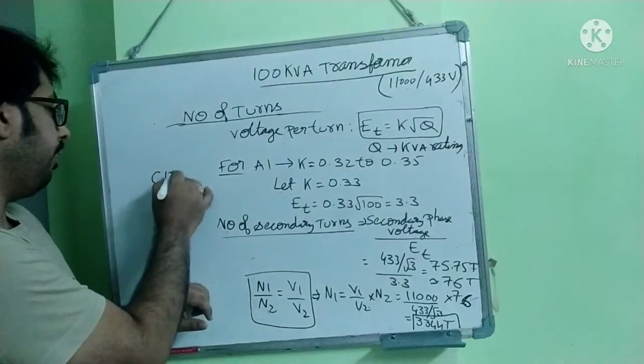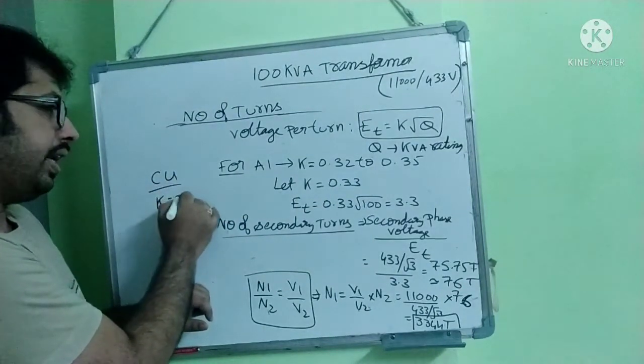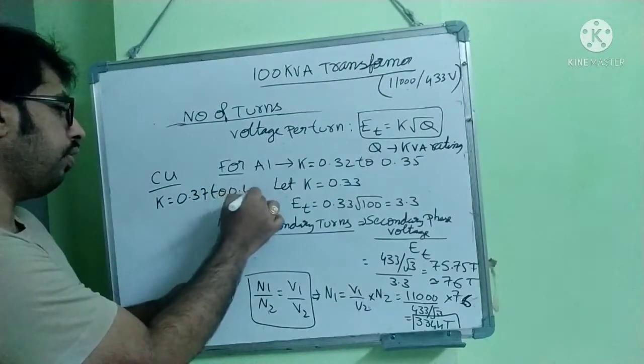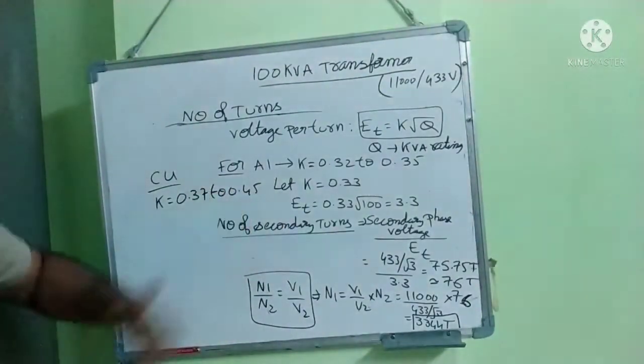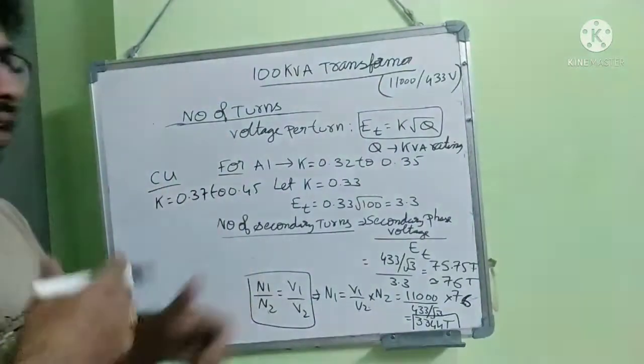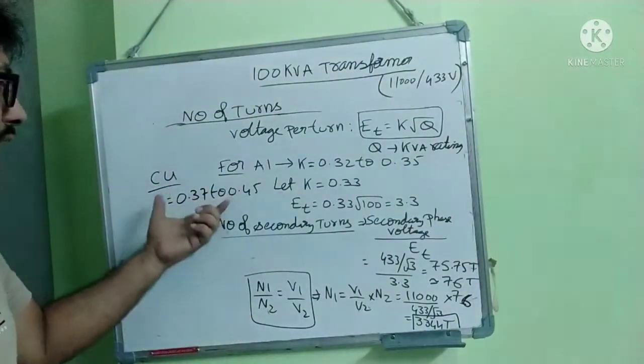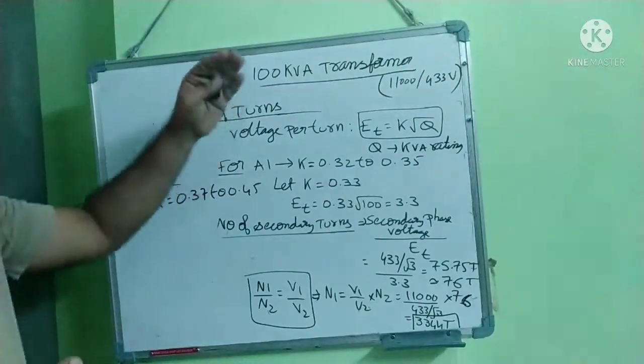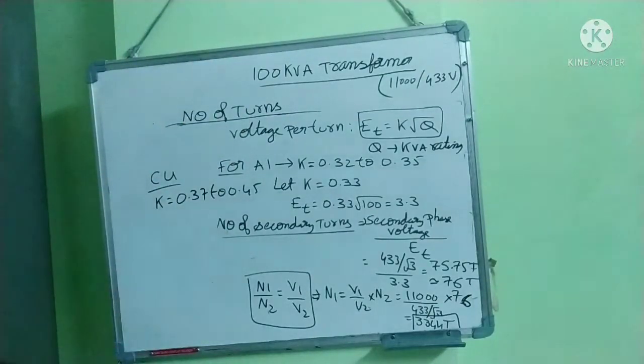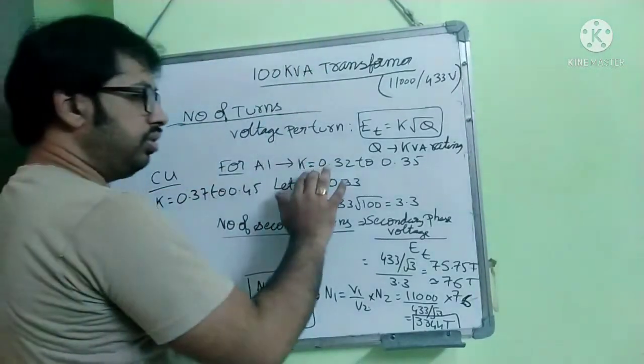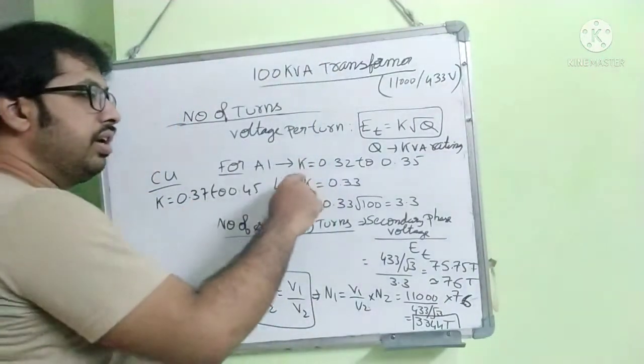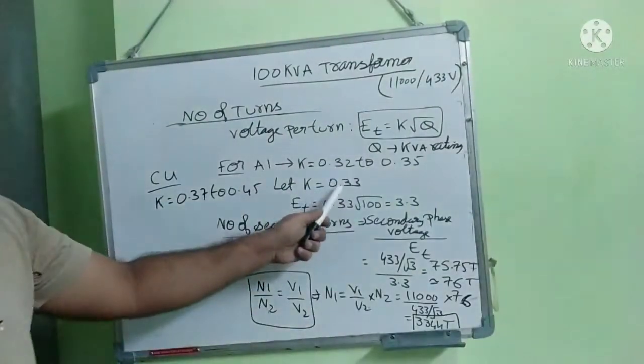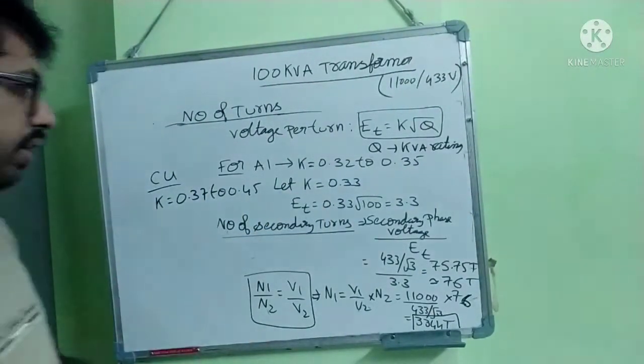For example, for copper, K value should be taken as 0.37 to 0.45. This is through experience, designing many times. If we take this, this is the best value of K where the losses will be under the specification control only. So K value for 100 kVA transformer, since you are using aluminum winding, you take K value as 0.32 to 0.35 in between. So I am taking 0.33.